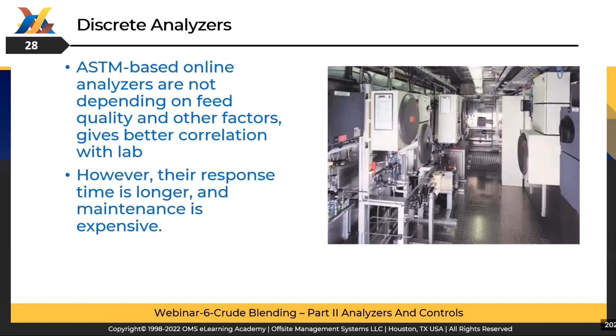As an example, next slide, please. The process gas chromatograph analyzer is a common type of discrete analyzer used in analytical chemistry to separate and analyze compounds that can be vaporized without decomposition. Despite its high maintenance requirements, this technology is the only available solution for many applications where multiple components shall be measured with high accuracy. This method also requires the supply of high-quality carrier gases like nitrogen, hydrogen, helium, argon, with a very high purity of about 99.95%.